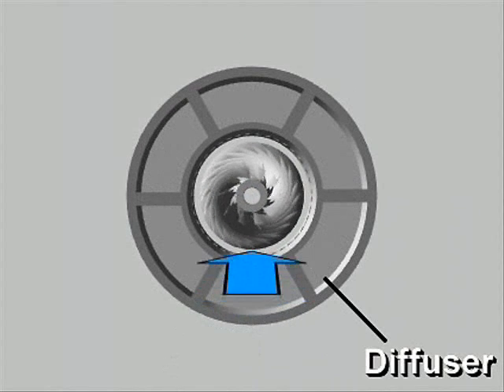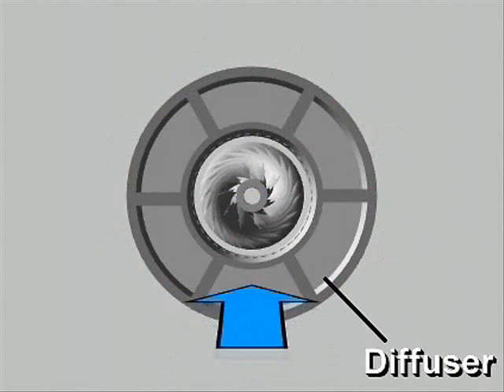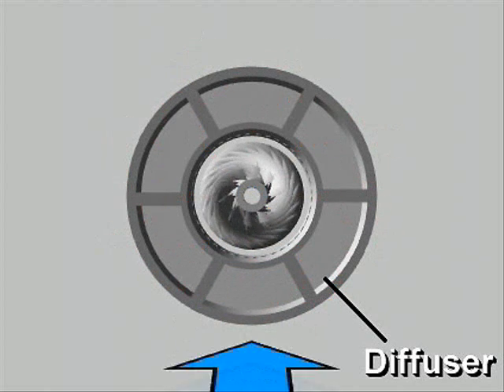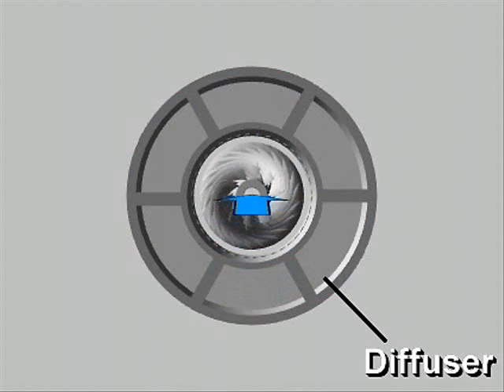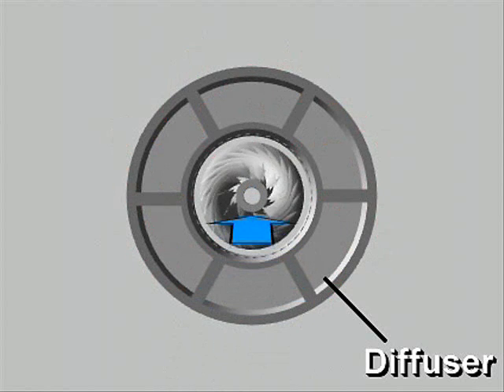That's where the diffuser comes in. As high velocity vapor moves radially outward through the diffuser, the flow area increases, slowing the vapor and increasing the static pressure. Some centrifugal models have diffusers with vanes or pipes which change flow direction and further slow the vapor.